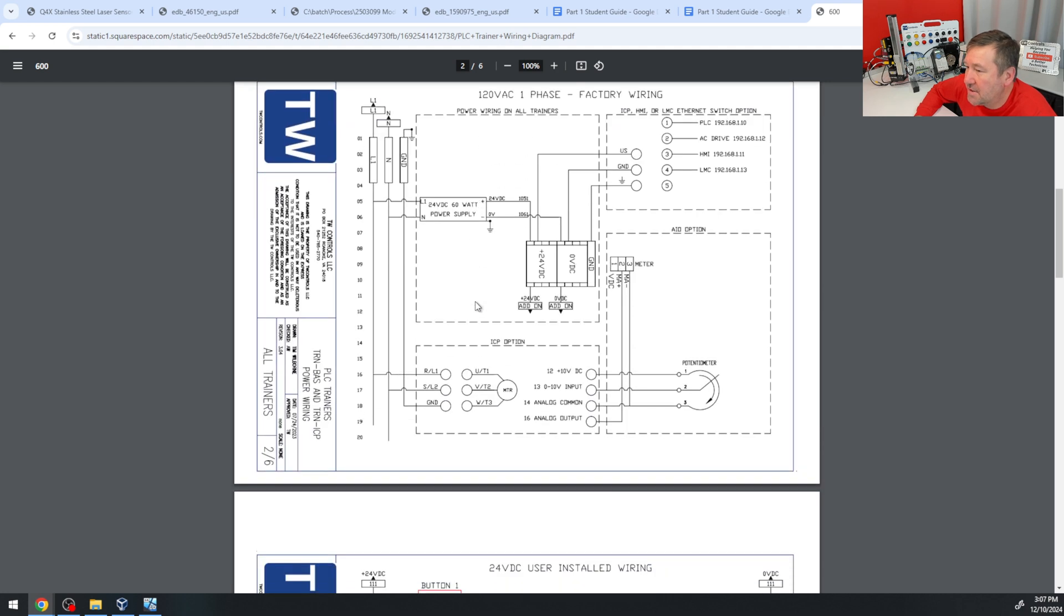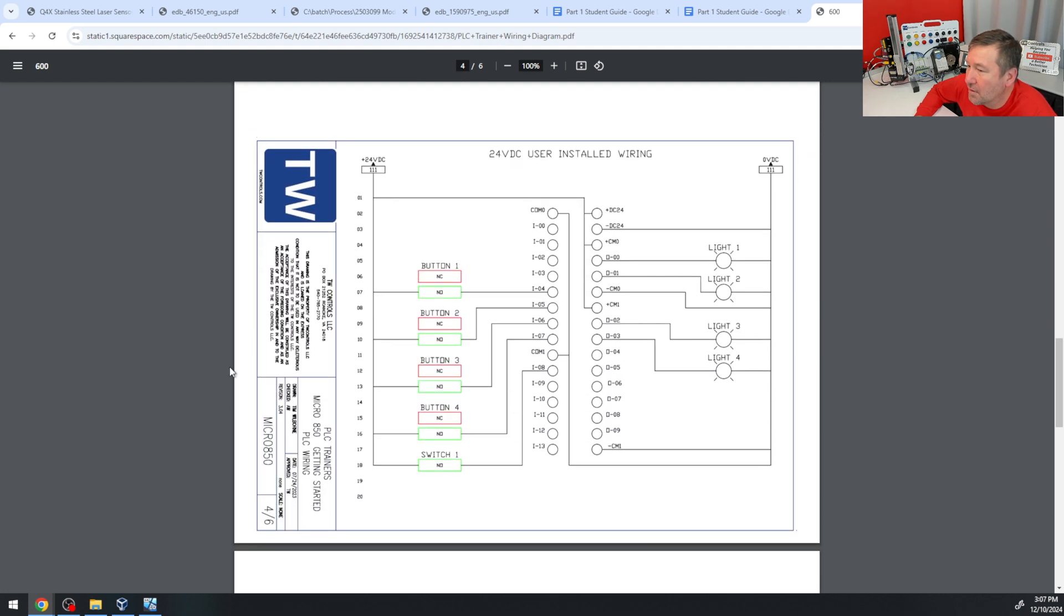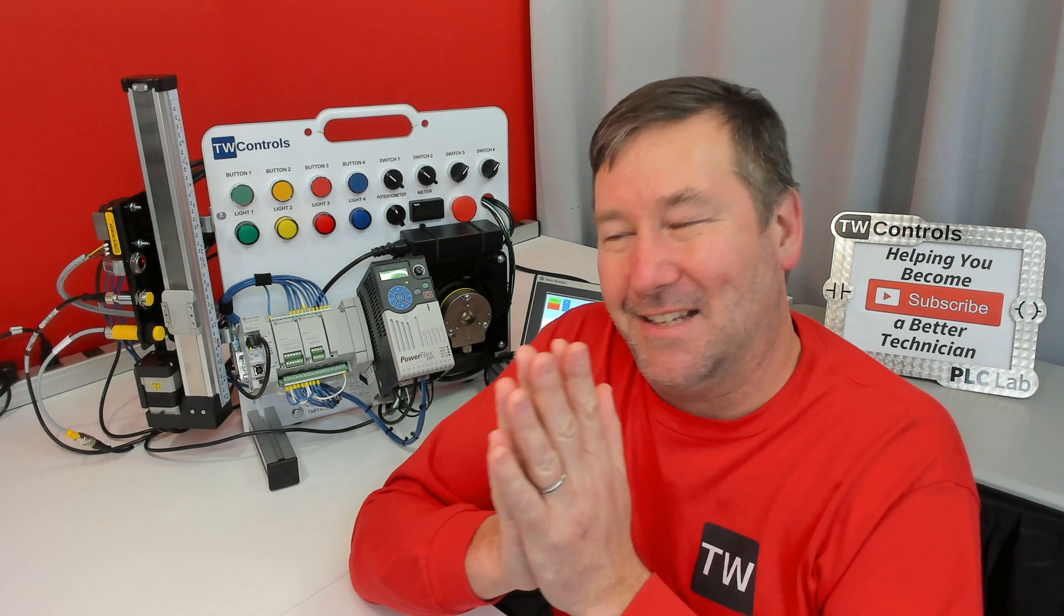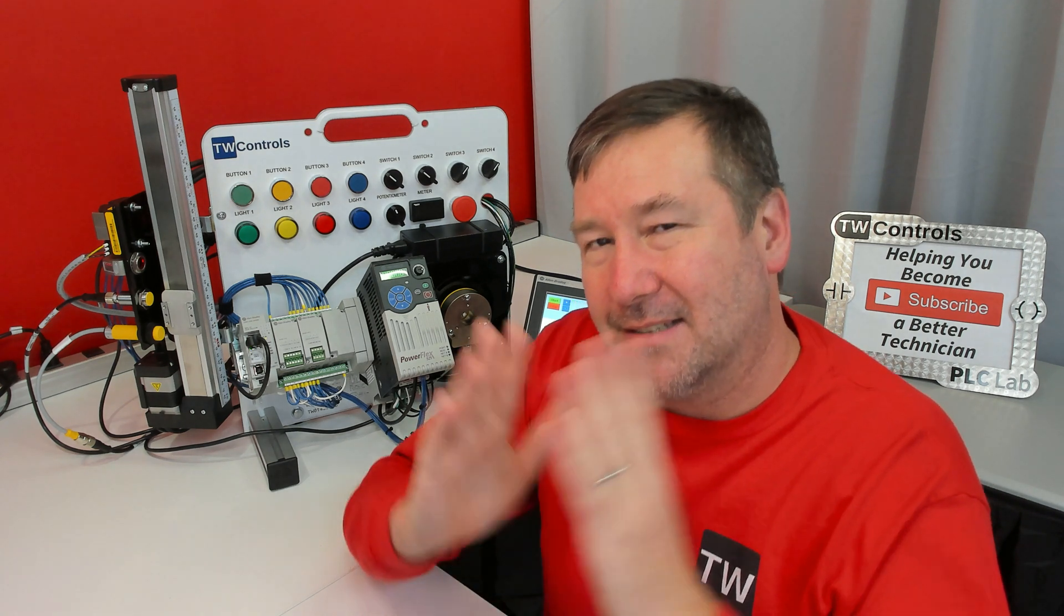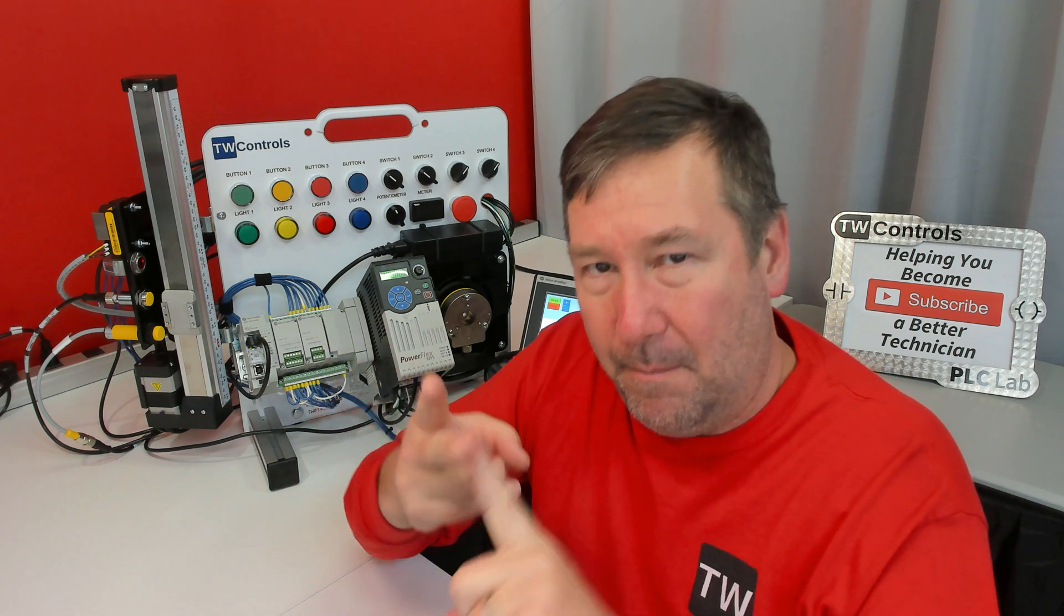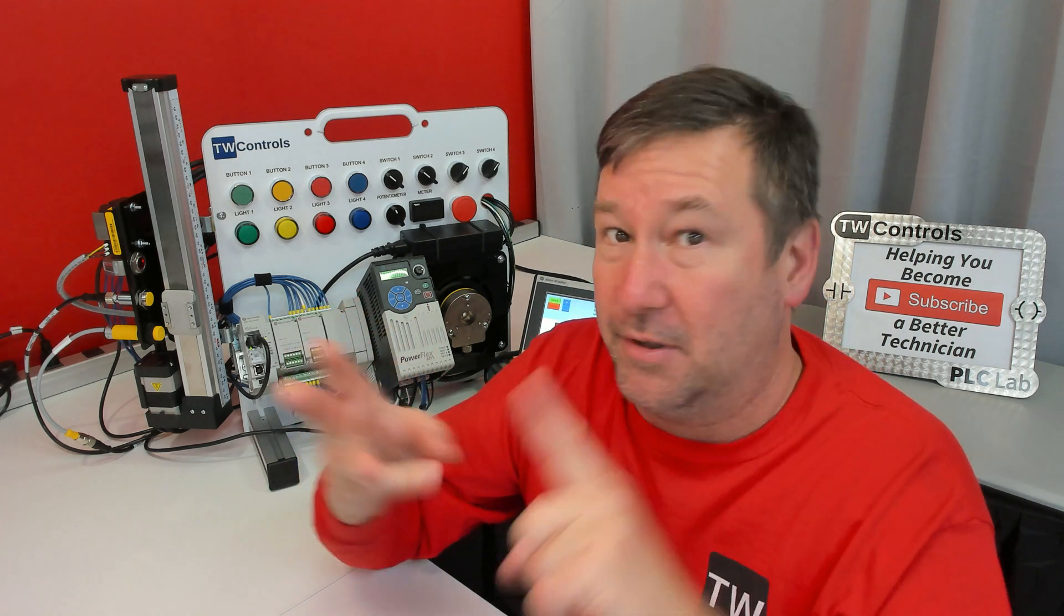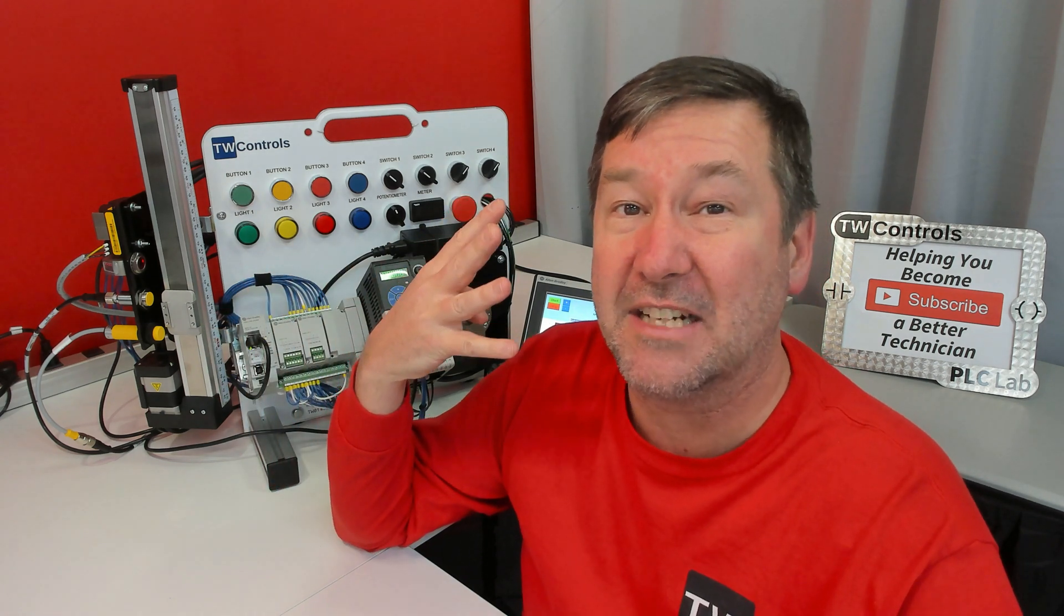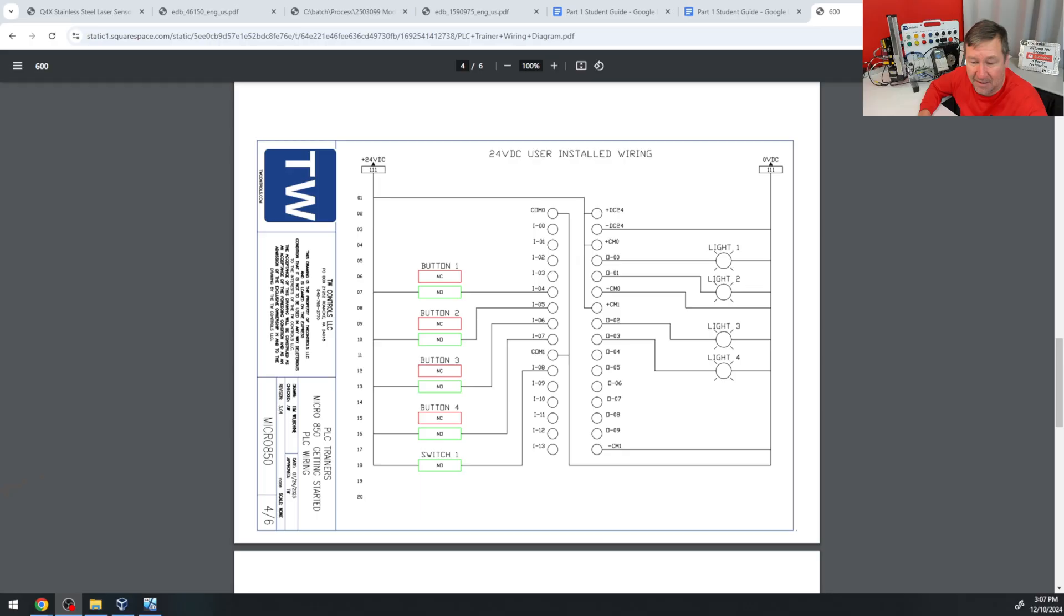And let's open it up. And let's go down to page 4. That is for the Micro 850. And you'll notice, as opposed to the CompactLogix version of this, this just is a COM0. Now, this is the argument that I see made up in the comments a whole lot, is a lot of people would have told me that common, the minus 24 volt of your power supply, neutral, and ground, are all the same thing. Those are four incredibly different items.